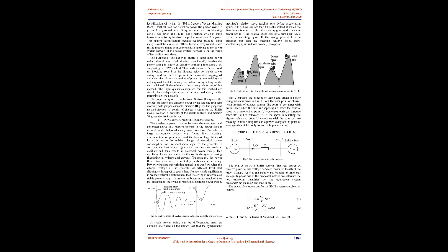One way to improve the functioning of the distance relay for power swing conditions and heavy loads is to change the distance relay's characteristics. The MHO characteristic angle adjustment is given in 3. Other similar methods include changing the zone shape of the distance relay, a supervisory zone tripping scheme, studying the load encroachment characteristics, etc. 3. All these methods are characterized as zone changing characteristics.